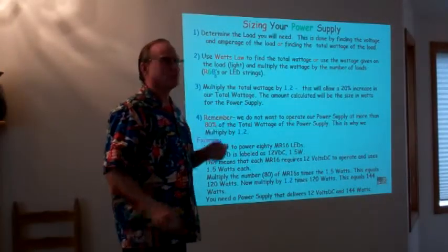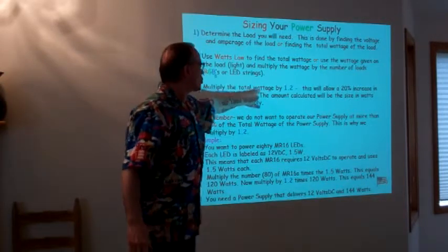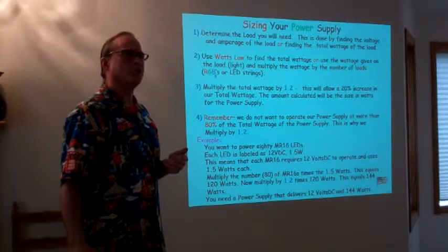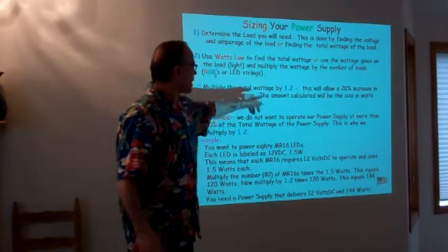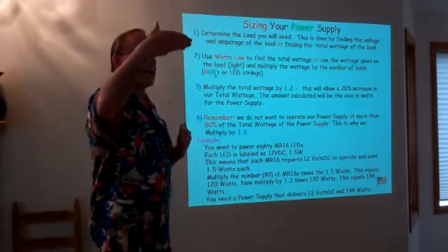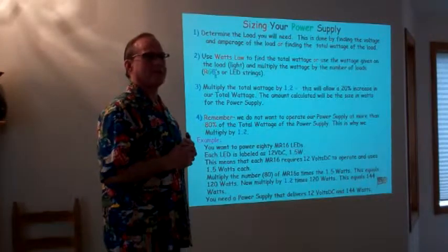doesn't develop. I'm saying to go ahead and take the wattage that you need, your total wattage, the amount you need, multiply that by 1.2. What am I doing? I'm now taking 100%, but I'm now adding another 20% to that.